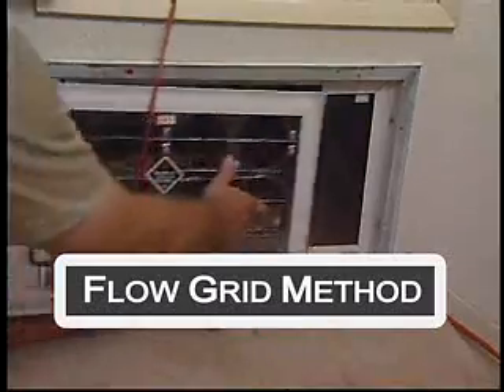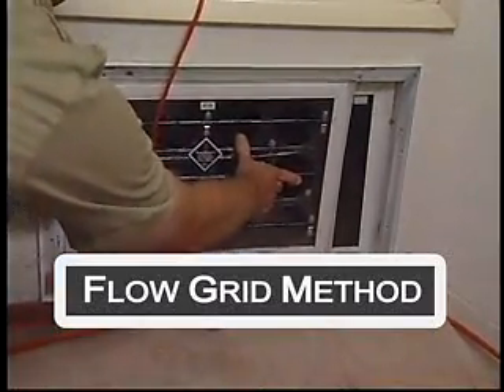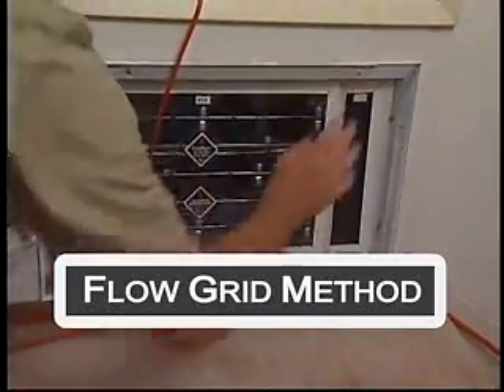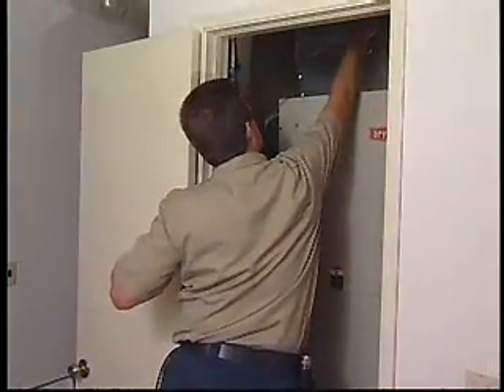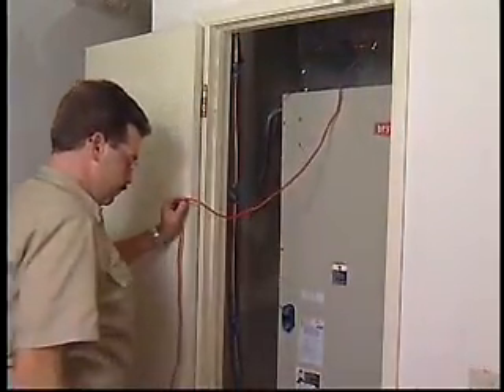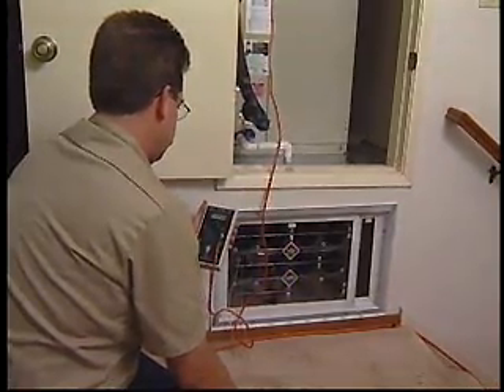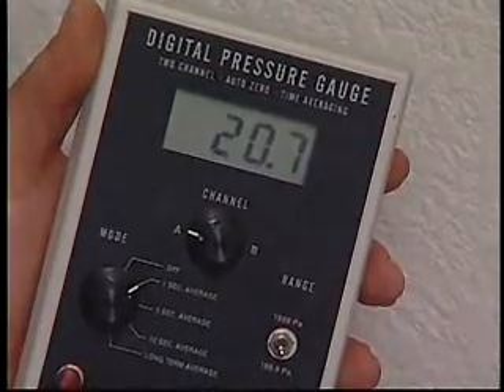Other than the temperature split method, is there another way to measure airflow? Well, another way is with the flow grid, which is a new device which you actually put in where the filter would normally be. You take a few pressure measurements, and from that you can get a real accurate measure of how much air is flowing through the inside coil. It's a really excellent way to do it.